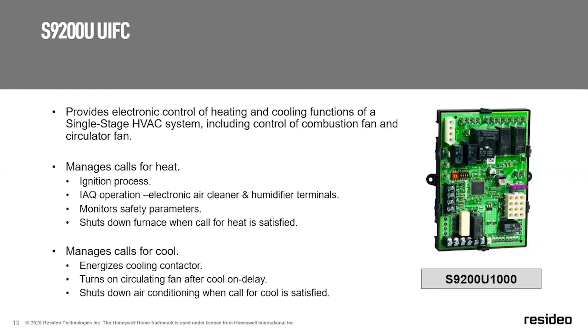And this board comes with different wiring harnesses. They're all labeled by letters, and the installation manual will tell you, if you're replacing this OEM board, which harness you're going to use. So it's really plug and play. It will also shut down your air conditioning when your call for cooling is satisfied. So it's a great truck stock item that gets you out of a lot of jams. It does have a replaceable fuse, which is that purple fuse there on the right, and all the terminals are labeled. And again, plenty of Molex connectors so you can choose which one is correct for your application.